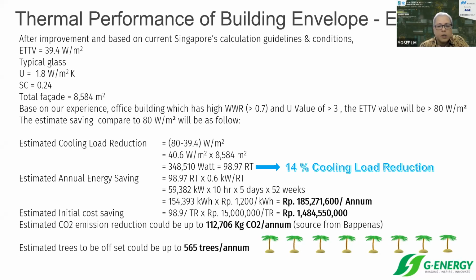Many projects used a single glazing type, so the ETTV value ended up quite high. In 2012, I did two projects, both new developments. At the time, probably not many people were aware of the building envelope method, so when they designed the envelope, they chose single glazing with low, not so good thermal properties. After we did the ETTV calculation, we ended up with a value of up to 80 watts per square meter.